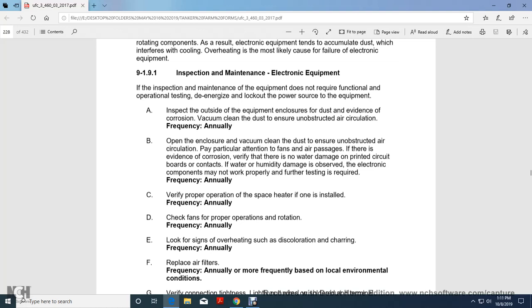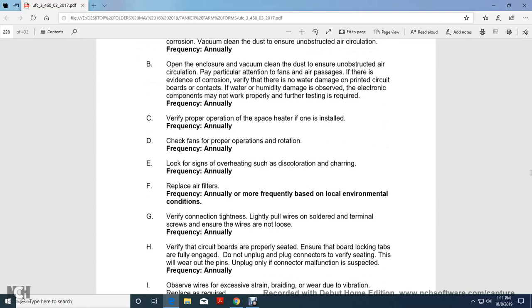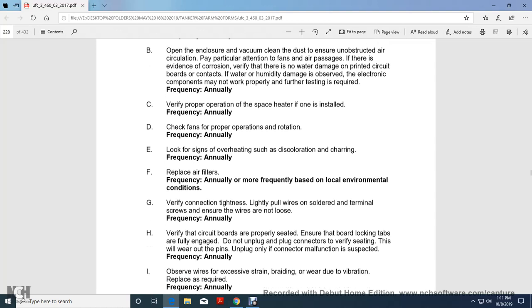Open the enclosure, vacuum clean the dust, and ensure unobstructed air circulation. Pay particular attention to fans and air passages. If there is evidence of corrosion, verify that no water damage is present on the printed circuit boards or contacts. If water or humidity damage is observed, electronic components may not work properly. Further testing is required annually. Verify the proper operation of space heaters, if one is installed, annually. Check the fans for proper operation and rotation annually. Look for signs of overheating and discoloration annually.